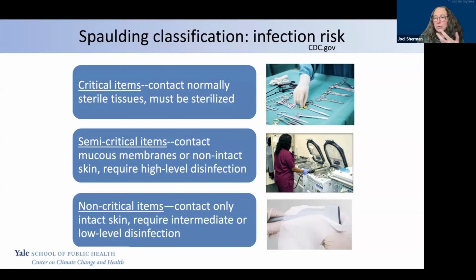When you eat at a restaurant, you're using silverware that someone else has used before, but it has been disinfected. So those require high-level disinfection. These two categories go down to the central sterilization supply department in the hospital. The last class here is non-critical items, things that contact intact skin, like a blood pressure cuff, or what you're seeing here, an image of an ultrasound probe. That's just going on your skin. Those things don't need to be sterile. They can actually be cleaned at the point of use. So you're seeing someone wiping down this ultrasound probe with a chemical wipe.